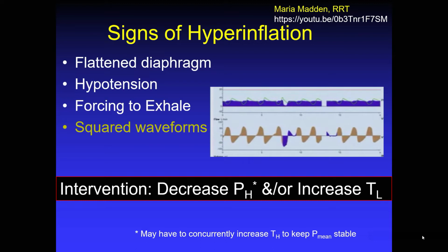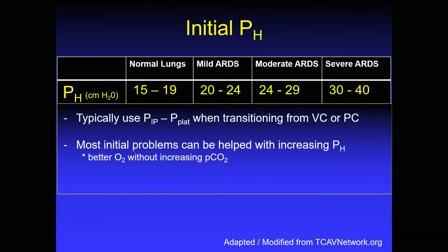Okay, so having touched upon some general observations about initially placing a patient on APRV and some of the pitfalls to look for, let's look at each of the APRV parameters more in depth and individually. P high. P high is the CPAP pressure setting. Again, in most instances, typically start in the higher 20s. In extreme rescue cases, I've gone as high as 45.